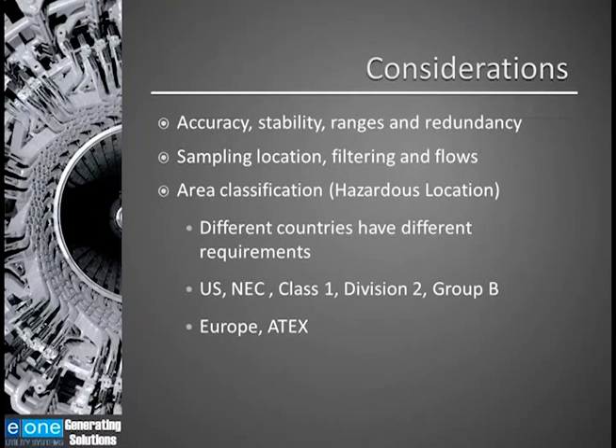So you want to be able to measure in the area of 70 to 100% hydrogen in air, and you want to be able to do 0 to 100% with hydrogen and CO2 and air and CO2. I also recommend you use redundant analyzers for two reasons. One, you'll have a 2 out of 2 voting, but also, in the event that one analyzer fails, you have another one as a backup.